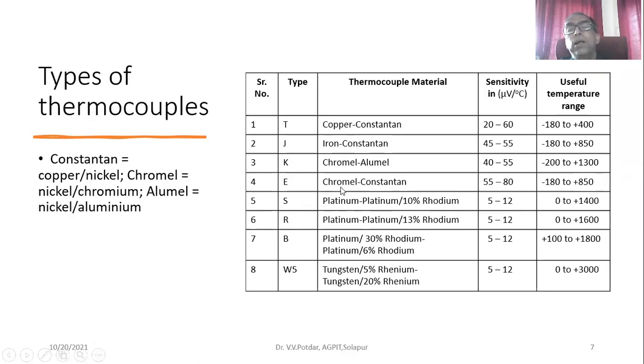E-type thermocouple material is chromel constantan. Sensitivity is 55 to 80, and useful temperature range is minus 180 degrees Celsius to plus 850. Then I have got S-type, platinum plus 10% rhodium. Sensitivity is lesser, 5 to 12, but the useful temperature range is 0 to plus 1400. In R-type, platinum plus 13% rhodium. Sensitivity is same, but the temperature range is broader now, 0 to plus 1600 degrees Celsius.